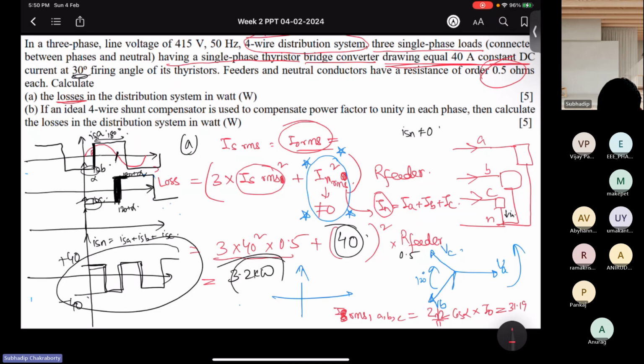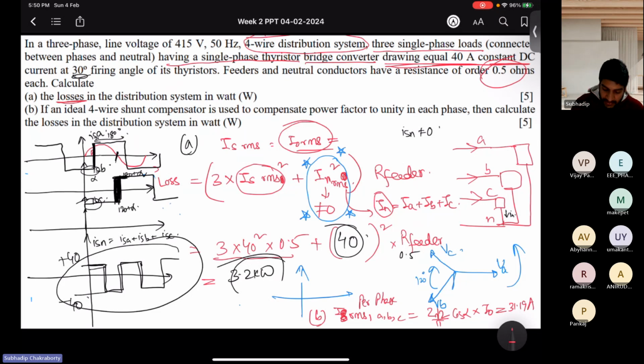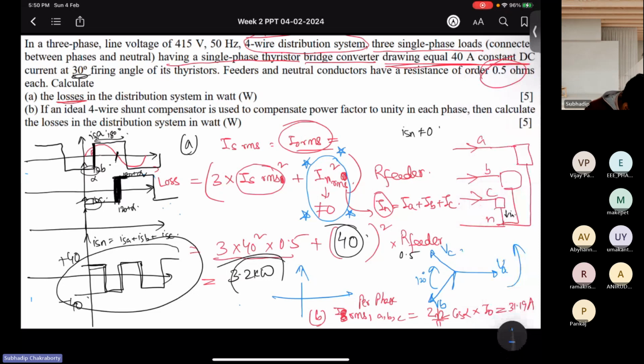So please do with me, right? It will benefit you. So after compensation for part B, when you do the per phase power balance, then you will see that the current amplitude has reduced to 31.19. Earlier it was 40. Now the RMS fundamental, which is after compensation, it is 31.19. So if you see, then what is the loss in this case? And will neutral current be zero after compensation? Anyone? Hello? 31.19 itself. Yes. I am asking that, okay, you have compensated and found out 31.19. Now what I am asking, after compensation, will the neutral current be zero or not?